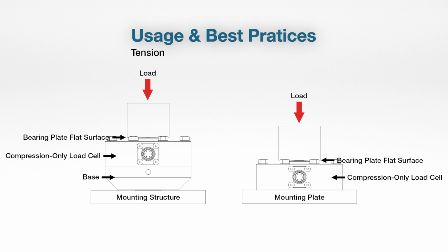And we have a couple examples of what this would look like. Again, we have a compression-only cell with the base installed. We have a bearing plate with a flat surface. I'm going to single point of contact on that. And again, hardened to the specification. And then the compression-only load cell with no base installed on a mounting plate. Again, with those same scenarios.